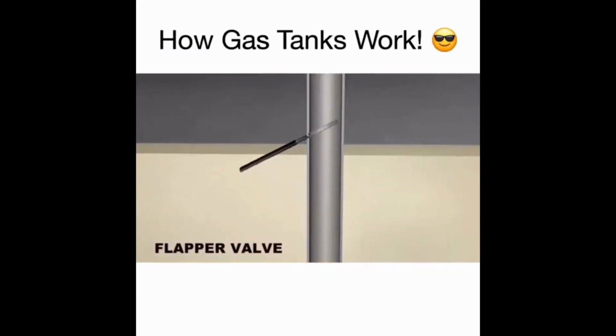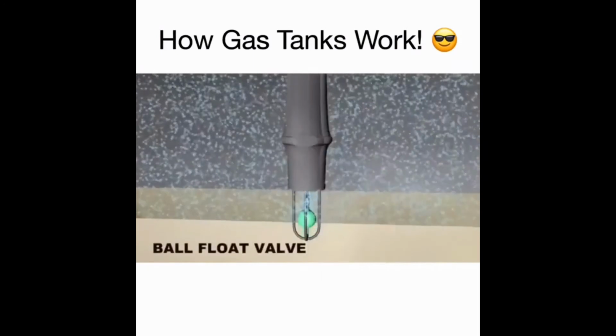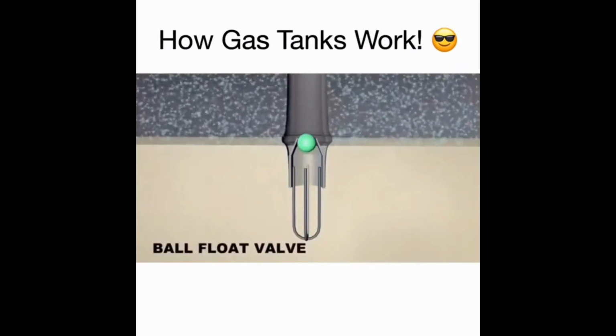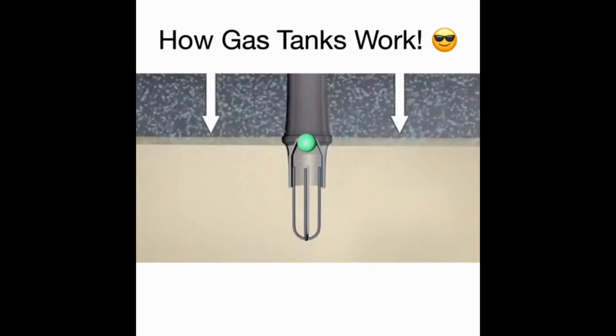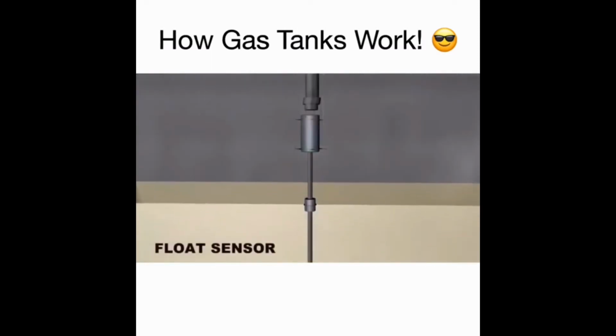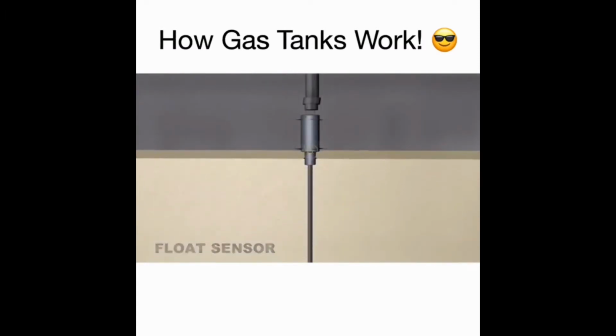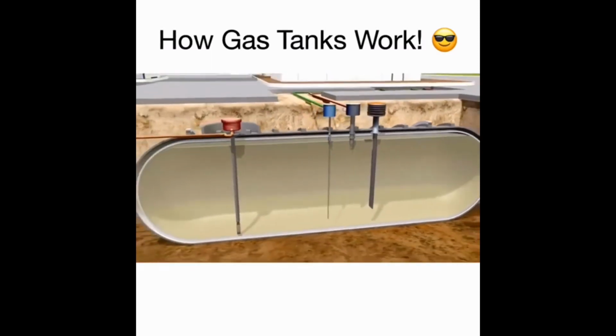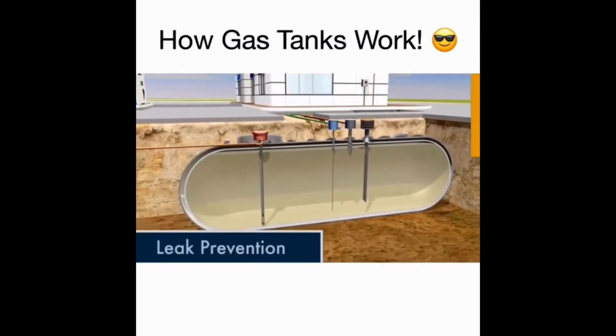A flapper valve automatically cuts off the flow of fuel into the tank, while a ball float in the vent pipe prevents vapor from escaping. The pressure of vapor within the tank then prevents additional fuel from entering. A float sensor alerts the operator if fuel reaches the target level. Once fuel is in the tank, it's important to make sure it stays secure until it's dispensed. That's why leak prevention is another essential part of the safety story.